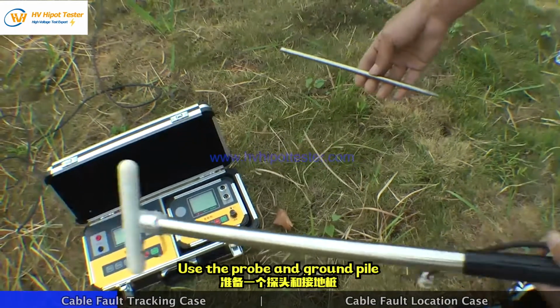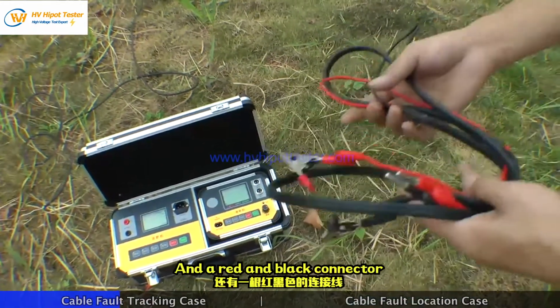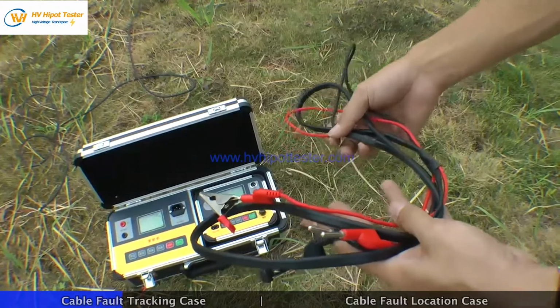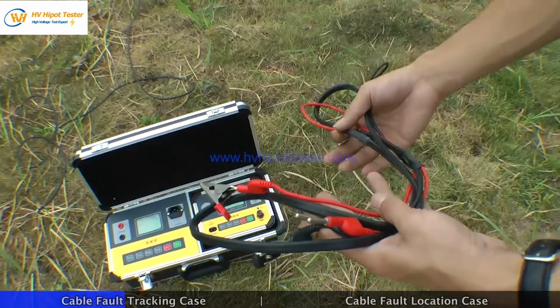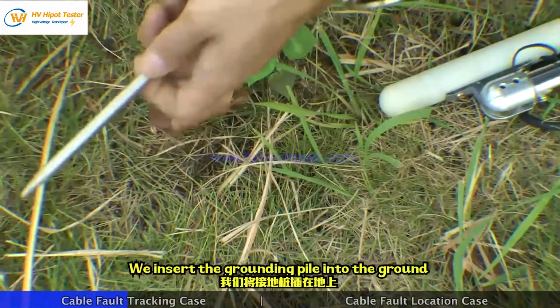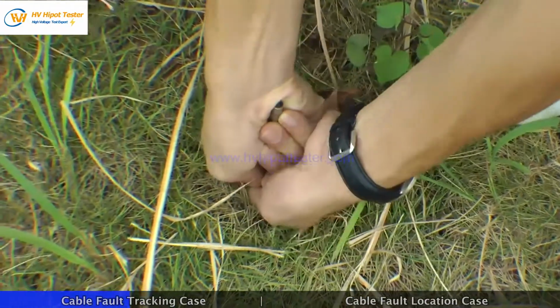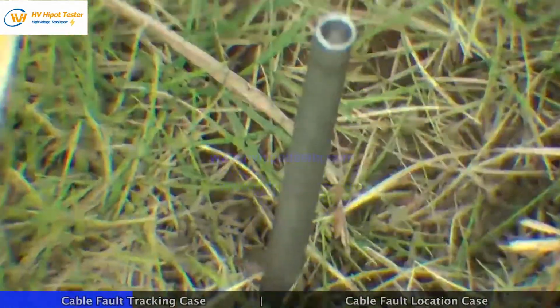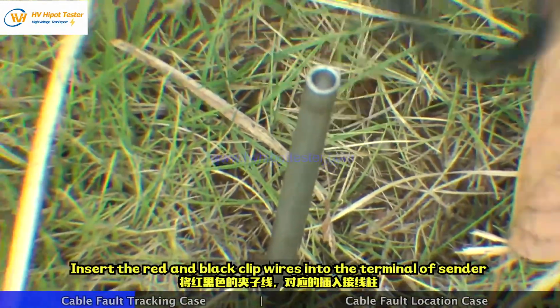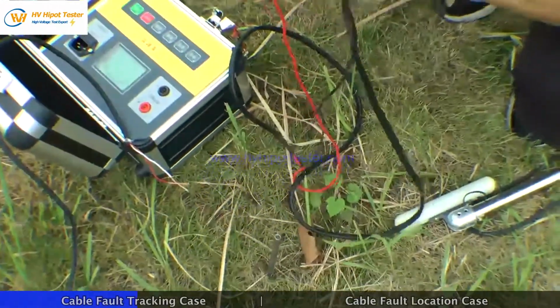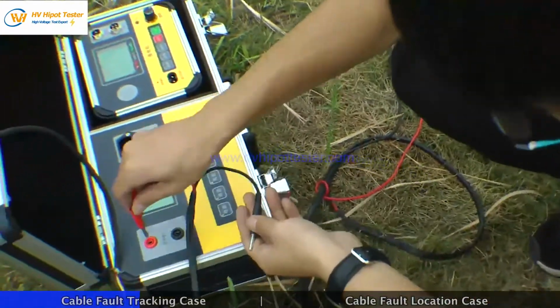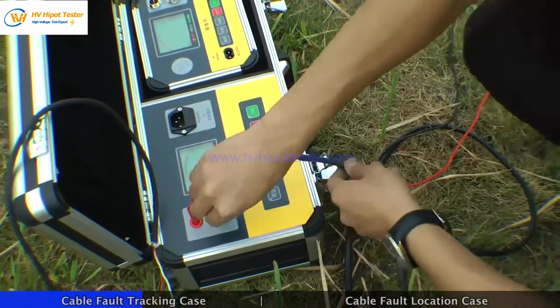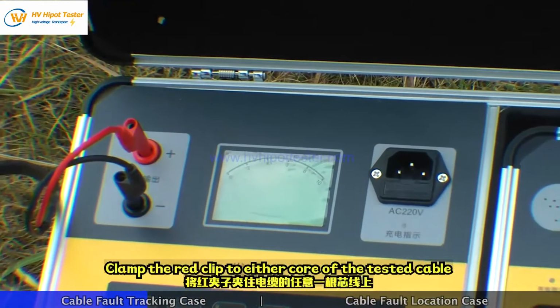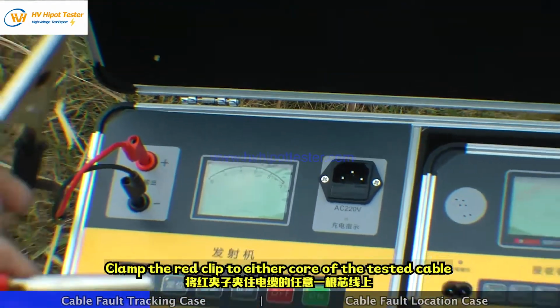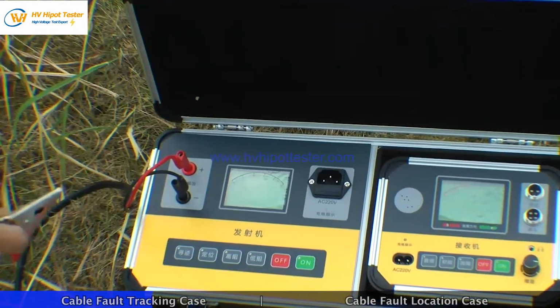Use the probe and ground pile, and a red and black connector. We insert the grounding pile into the ground. Insert the red and black clip wires into the terminal of the sender. Then, clamp the red clip to either core of the tested cable, and the black clip to the grounding pile.